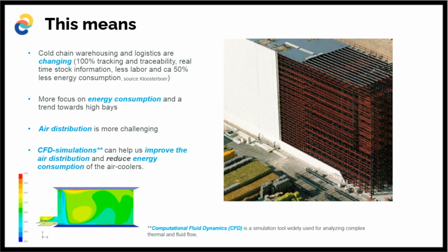And quickly, what is a high bay? You see a little picture of one being built there. They are around 40 meters high, 100 to 150 meters long, and 60 meters wide or so. They're quite high and big, and fully automatic. The point is, because of these high buildings, the air distribution is getting more and more difficult. You have to get all the air nicely distributed in these high bays. And therefore, there are CFD calculations and simulations that can improve this air distribution and where we can reduce the energy consumption. By the way, CFD is computational fluid dynamics. It's a simulation tool where we can predict what the temperature and air distribution throughout the high bay is going to be. Very handy.